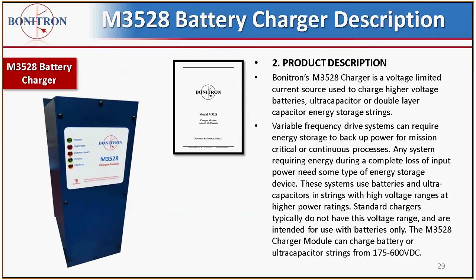Now, with the outage ride-through, there are some ancillary units that are required. The one we're going to talk mainly about is the 3528 charger. It's a voltage-limited current source, and it's used to charge batteries, ultra caps or electrolytic caps, which we use all three energy storages, and that's dependent on your specification. So one of the advantages of Bonitron is we can actually size the energy storage to the exact requirement. A lot of ride-through solutions, say UPSs, you're stuck with 5 minutes, period, regardless of whether you need just seconds of backup. They don't provide any lower than 5 minutes, is what I've found.